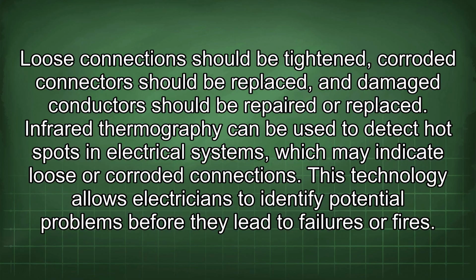Infrared thermography can be used to detect hotspots in electrical systems, which may indicate loose or corroded connections. This technology allows electricians to identify potential problems before they lead to failures or fires.